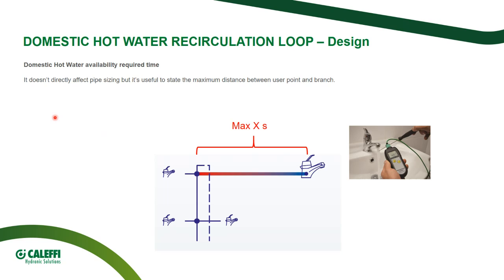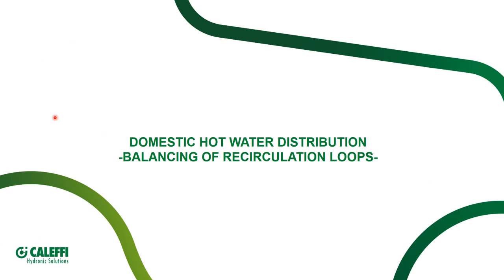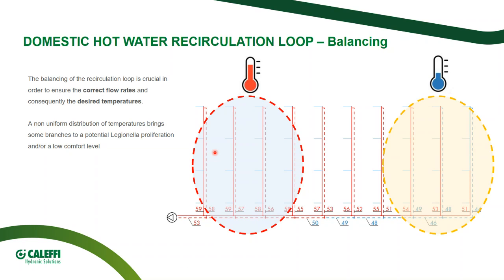Then these were some comments and some tips concerning the sizing and the design of them, just a few. Another big headache is the balancing of them, because so far the system is sized, the system is designed, but I have to grant somehow that the distribution of the domestic hot water temperature throughout my big system is right. So this is a common situation of imbalanced system with a centralized recirculation pump and many risers serving a different washroom. We can always identify 3 areas, the closest to the pump where the temperature is even more than enough.